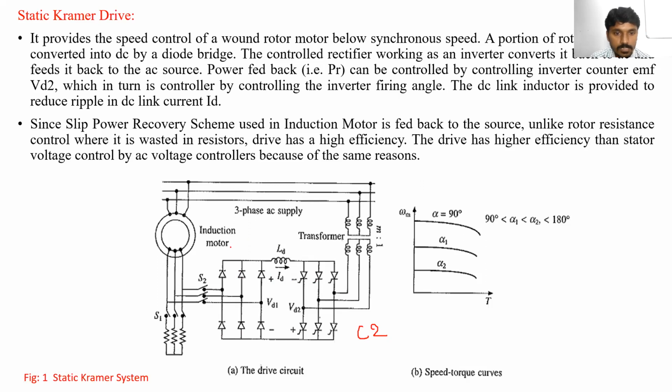This design is called a static Kramer system, since the slip power recovery scheme is used and the slip power of the induction motor is fed back to the source. By using this slip power recovery scheme with the static Kramer drive, we can get back the energy and give it to the source, unlike rotor resistance control where it is wasted in resistors.